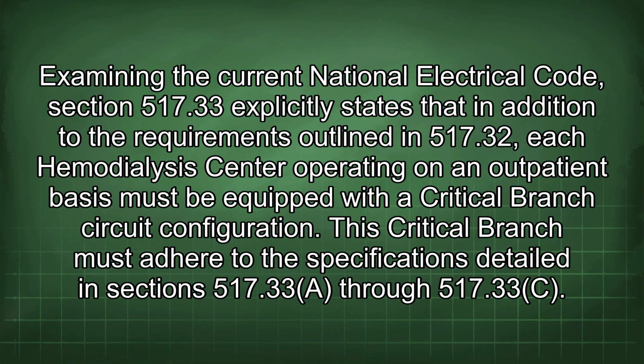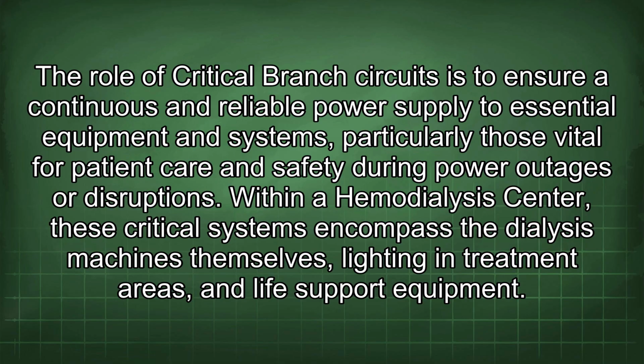Examining the current National Electrical Code, Section 517.33 explicitly states that, in addition to the requirements outlined in 517.32, each hemodialysis center operating on an outpatient basis must be equipped with a critical branch circuit configuration. This critical branch must adhere to the specifications detailed in Sections 517.33 through 517.33c.